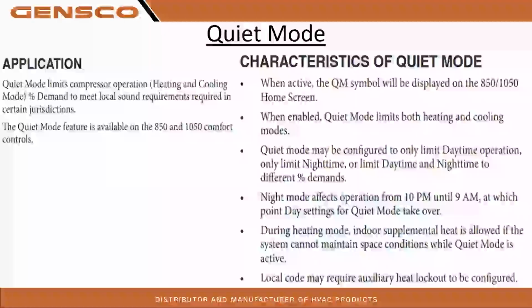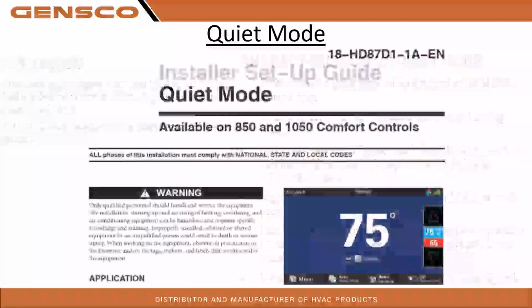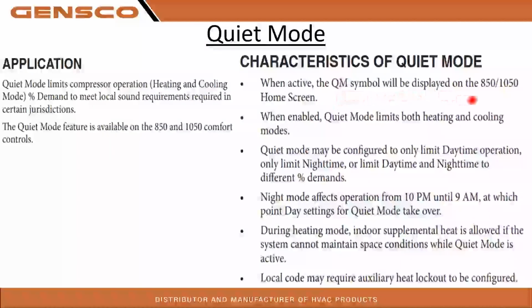Well, here's our quiet mode. When active, the quiet mode symbol would be displayed on the home screen. Quiet mode is the percentage demand. In heating and cooling mode, quiet mode limits compressor operation percentage demand to meet local sound requirements. Here in Seattle, they are pretty picky on quiet mode. So this really saves us in the city of Seattle, because they're making guys go back on jobs that have been inspected a year prior and relocate units because the neighbor complained that they're too noisy.